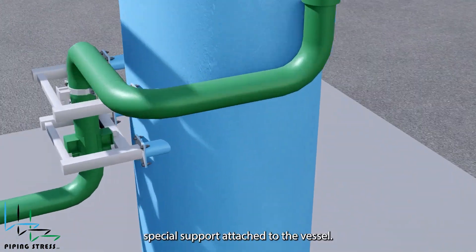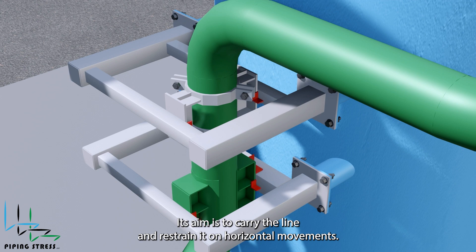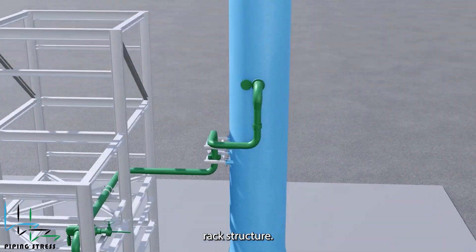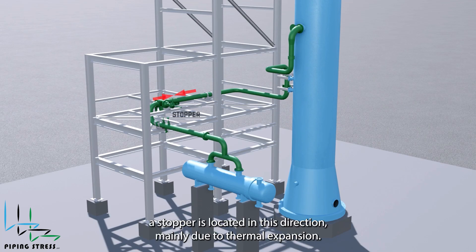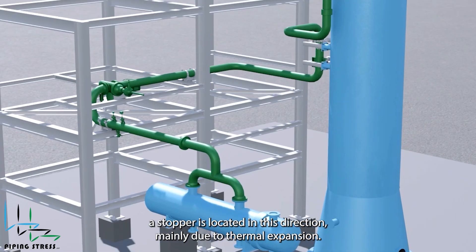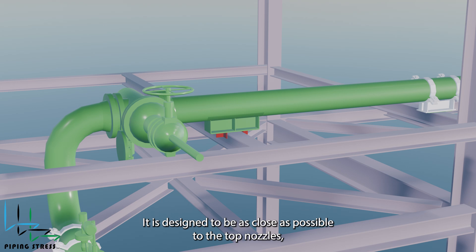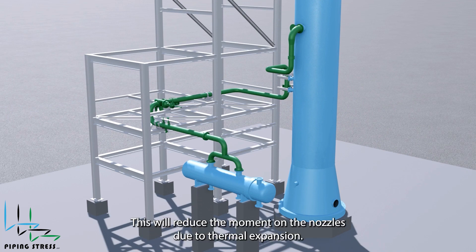The support is a special support attached to the vessel. Its aim is to carry the line and restrain it against horizontal movements. Following that, the line enters the pipe rack structure. A stopper is located in this direction, mainly due to thermal expansion. It is designed to be as close as possible to the top nozzles, which is also required for seismic loads. This will reduce the moment on the nozzles due to thermal expansion.